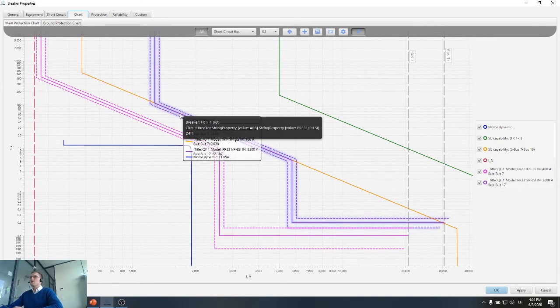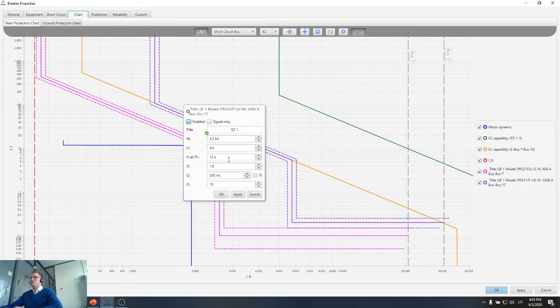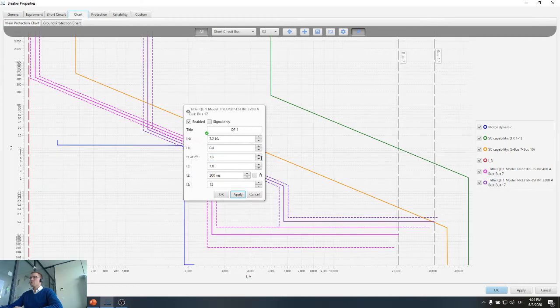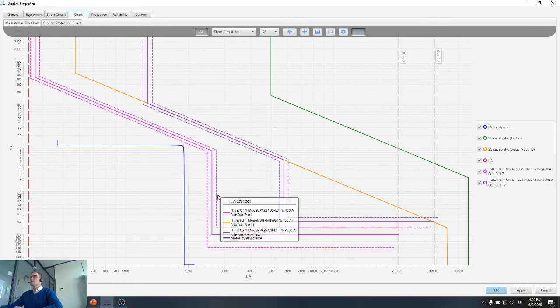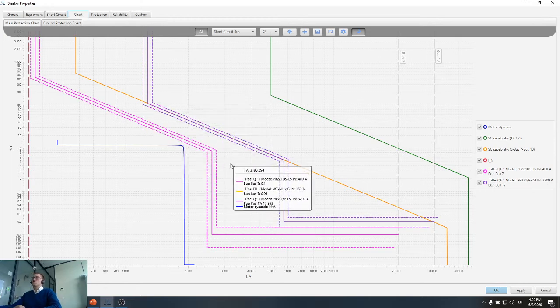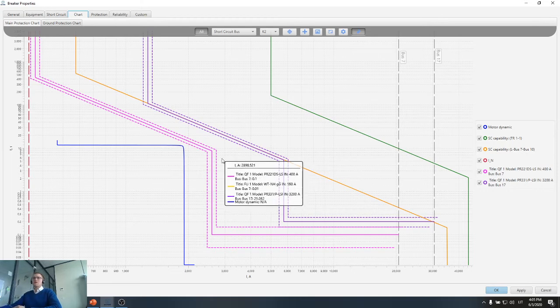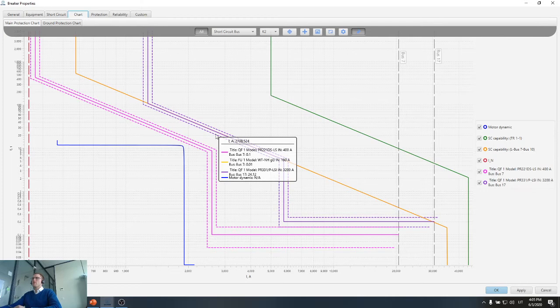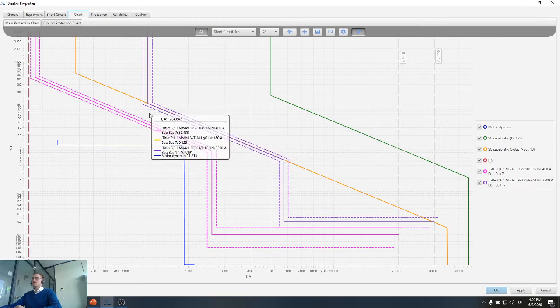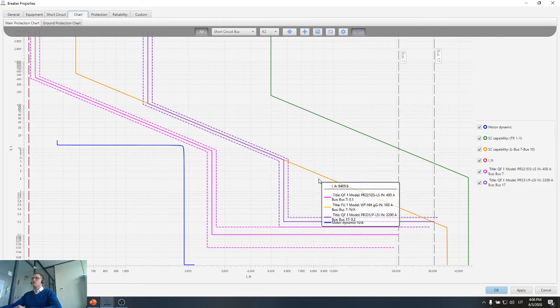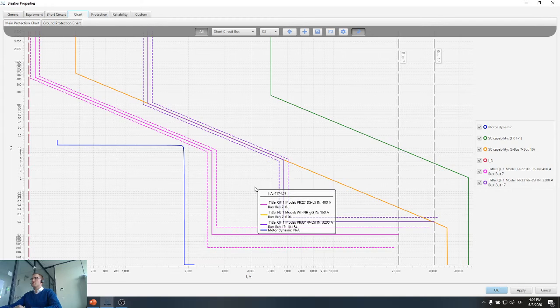So in order to optimize this, we can try to reduce the time here. However, I have only two time settings, like 3 and 12 seconds. So maybe I'll just set 12 seconds and leave it as it is. Otherwise I need to look for another breaker which would allow me to provide settings smaller than 3 or bigger than 12 seconds. But the idea is that in our software you can also add cable capability curves and selectivity charts, and ensure that backup protection will also protect the cable.